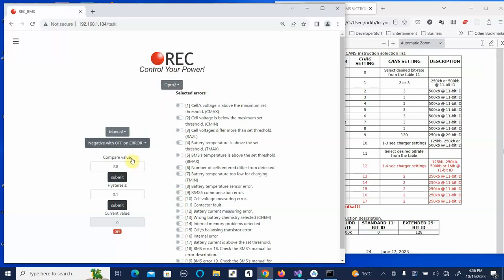So we'd set up number 2, and let's say we wanted to set it on a state of charge. Let's say when our batteries go below 50%. So we would just say compare, if it's 0.5, remember it's percent, with a 10% hysteresis. Let's make that 5%. We'll submit that. Oops, didn't. So it's 0.5 and 0.05. So this output now will close. We could turn on a buzzer, an alarm, an indicator, something showing that our capacity has gone less than 50%.